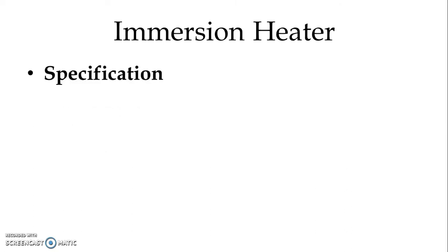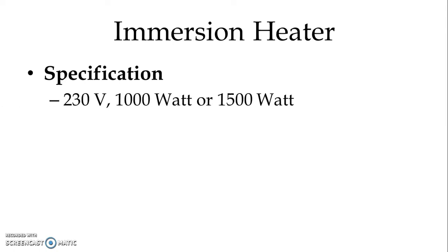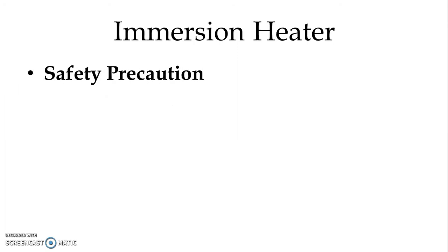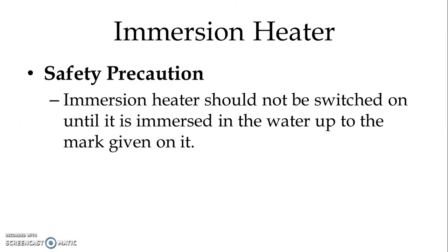Let us check the specifications for the immersion type of heater. The supply voltage is normally 230 volts, and immersion heaters are available in 1000 watt or 1500 watt capacities. As a safety precaution, we must ensure that the immersion heater should not be switched on until it is immersed in water up to the mark given on it.